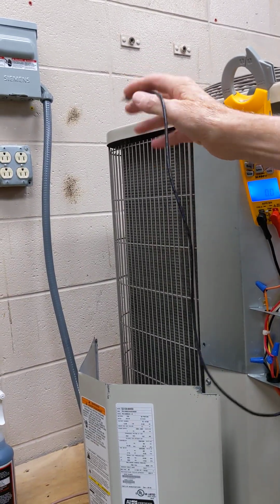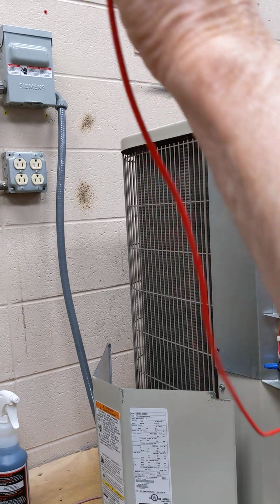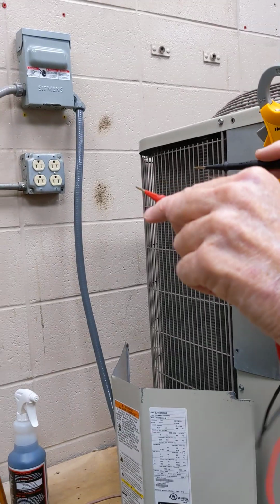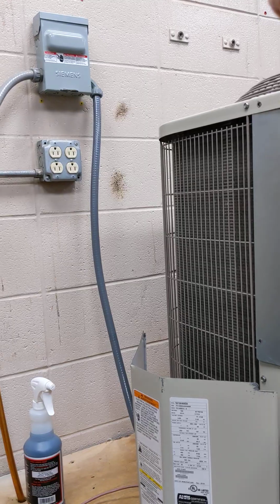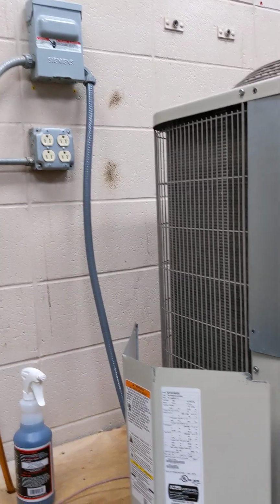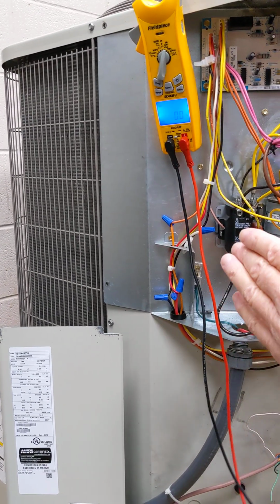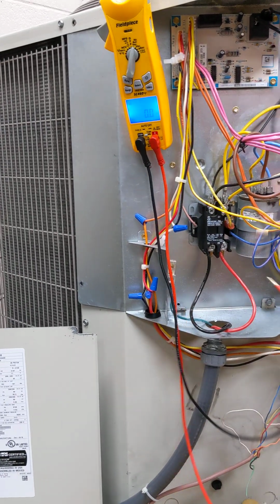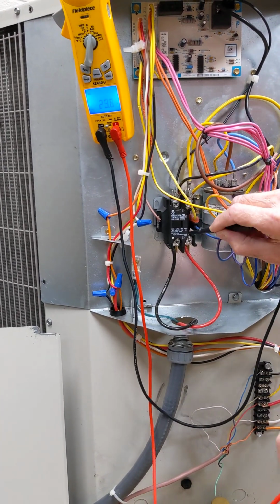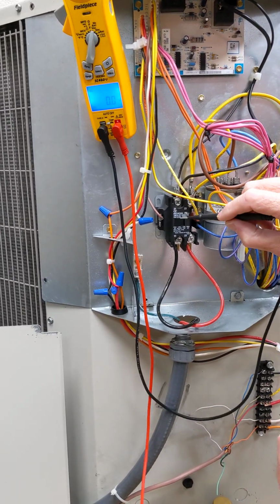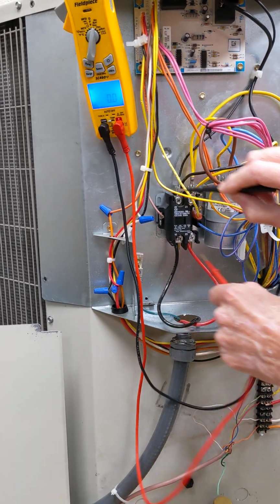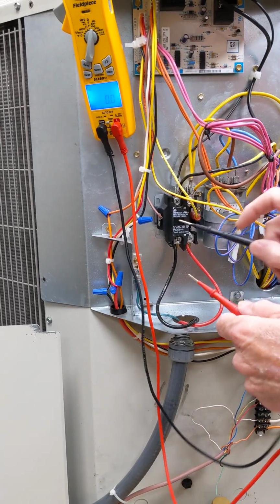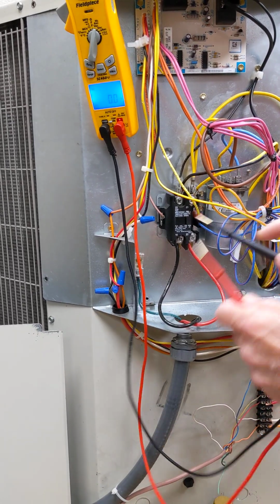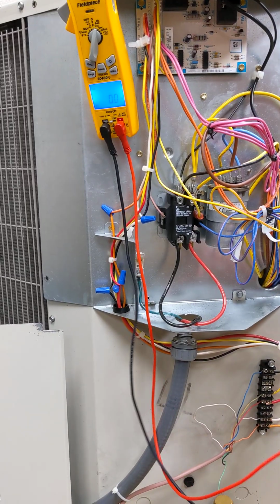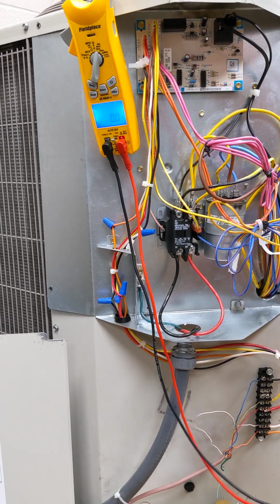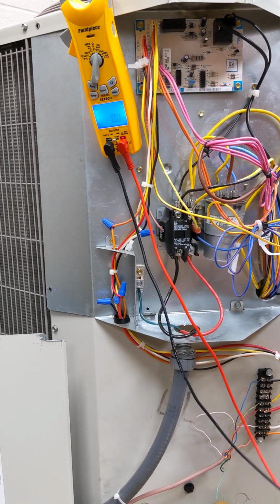It's a pull disconnect. But if I had fuses in there, I could do the crisscross applesauce, besides just checking it coming in, whether it's coming in top or bottom, and the out, do the crisscross applesauce. One, that'll tell me if the fuse is good or bad, because a fuse is just like the straight leg, it should let everything through. If I had a good fuse here and a good fuse here, this would work both ways. If I don't have one of the fuses good, it won't work one way and it will work the other way. And that's how you can identify which fuse is blown. That's extra tidbit for you.